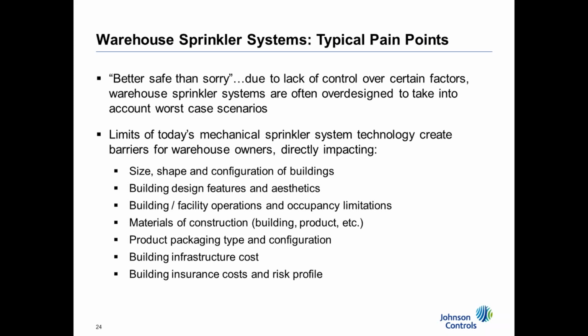And hence, just to account for that, you have 12 or 16 head designs, for example, in a ceiling-only ESFR system, and hence you end up requiring a lot more water and infrastructure to support that. So, going through the limits of today's automatic sprinkler system technology, you're limited in terms of what you can do in designing the building, what product you can store, and how you're able to store it. So what ends up happening is you're limited in terms of operational flexibility within the facility. It also ends up impacting the way you store your product, the way you package it, configuration, etc. It really hinders the flexibility within a warehouse, and then ultimately it ends up impacting the insurance costs and risk profile when you store products in your warehouse.